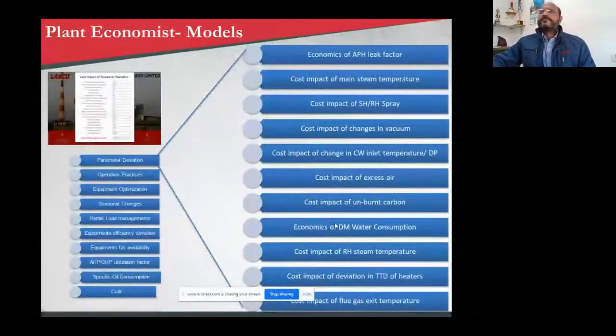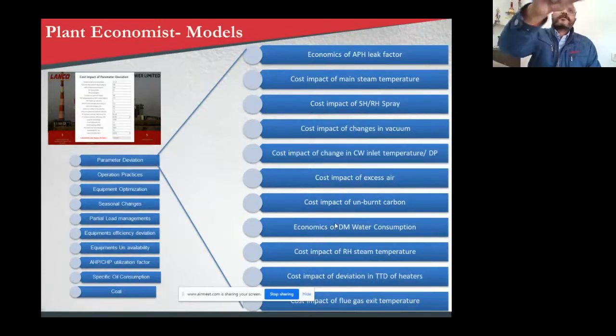So coming back to parameter deviation, if we go inside it, I will read out various parameters like air preheater leak factor, main steam temperature, reheater, superheater spray, vacuum. I will not go into the formulas for each. These formulas are generally given by every OEM in their manuals. We can convert those curves into formulas and calculate the impact on heat rate or aux power, and then further calculate it in financial terms. In the left top corner a screen comes to enter the values, and we get a calculated cost impact in rupees per day. Reheater temperature, DM water consumption, unburned carbon, terminal temperature difference, exit flue gas temperature, etc. are covered in these parameter deviations.